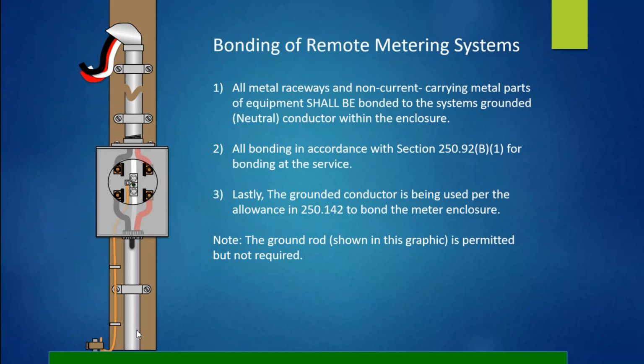And here we have the raceway going down to the structure. It doesn't have a bonding jumper on this because this was a perfectly cut hole. There weren't any concentric or eccentric knockouts. There weren't any impaired openings. So I used a bonding lock nut to make this application.